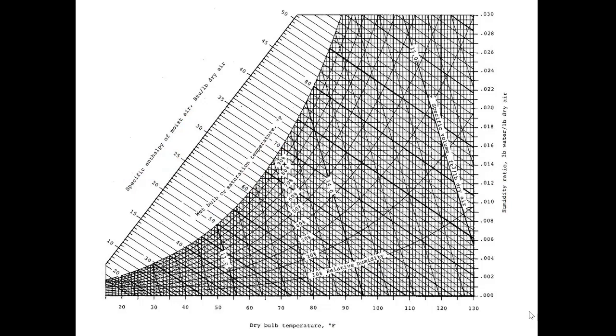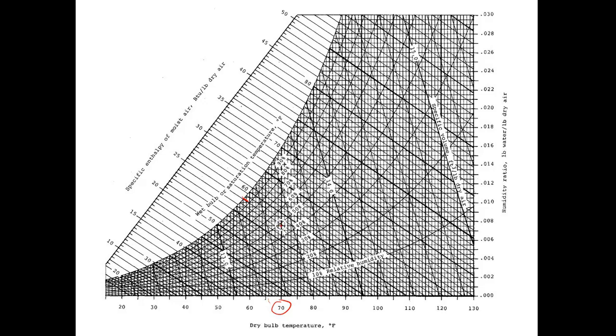All right, so let's do an example. And actually, we'll just go back to what we did from the recording when we had our sling psychrometer in my office. All right, here's the dry bulb temperature down here. So we're at 70, and the wet bulb temperature was 58. So we've been right, this line right here. All right, so 70 and 58. So let's see if we can line those up. So if we come up to 70, the black one here, and it'll line up with right about there, two lines down. All right, so let's look on here. Yes, right below the 50% line, relative humidity. So it looks like the sling psychrometer, right, you can see it was some hysteresis, it would move around a little bit. I guess it's right near that 50% that we had measured there.